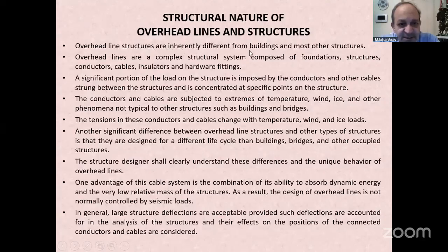Overhead line structures are inherently different from buildings or most other structures. Overhead lines are a complex structural system composed of foundation structures, conductors, cables, insulators, and hardware fittings. A significant portion of the loads on the structure is imposed by the conductor and other cables strung between the structures, and the load is concentrated at specific points on the structure. The conductors and cables are subject to extremes of temperature, wind, ice, and other phenomena not typical of other structures such as buildings and bridges.